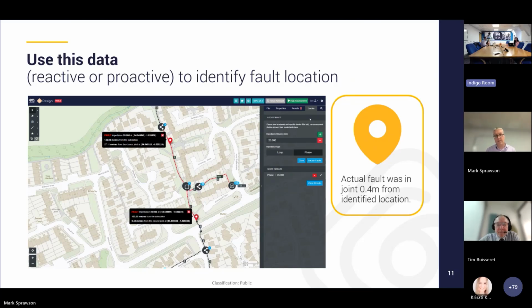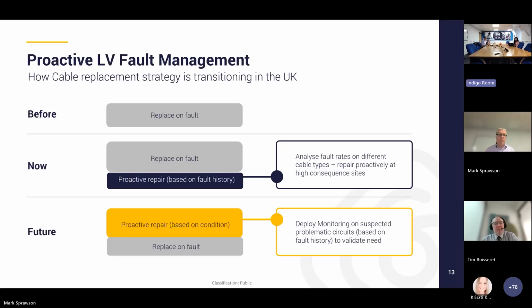And indeed, in this case, it was that bottom pin, the southerly pin there, and the actual fault was in that joint. It was 0.4 meters from the identified location. And the DSO was able to go there and repair that fault before it actually developed. So nowadays, what grid edge intelligence is driving in this operational sense is this kind of approach to LV fault management. Historically, cable replacement strategy and fault management was all replace when it fails. That's how it has been for decades. Now, that is still by far the majority.